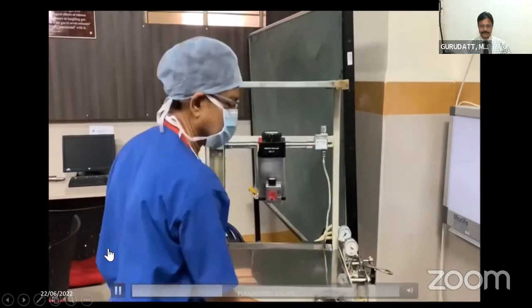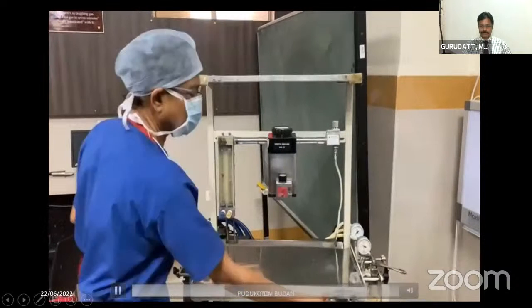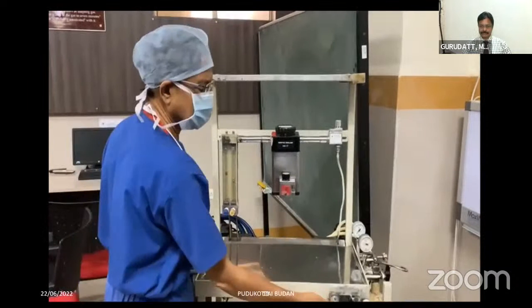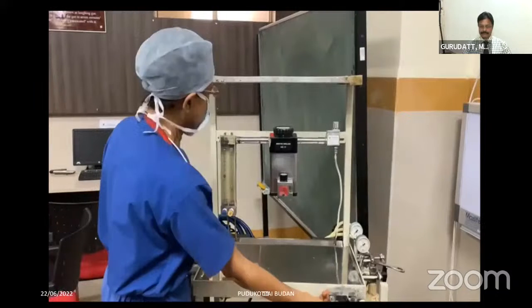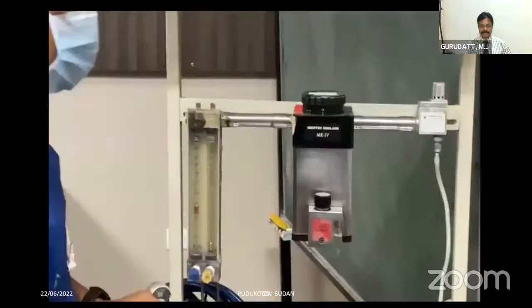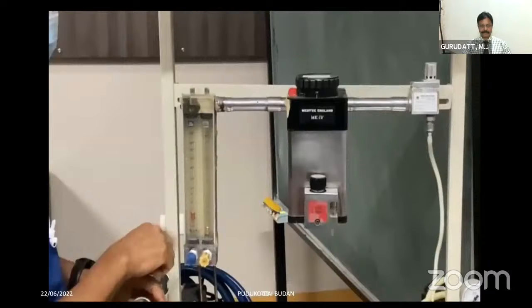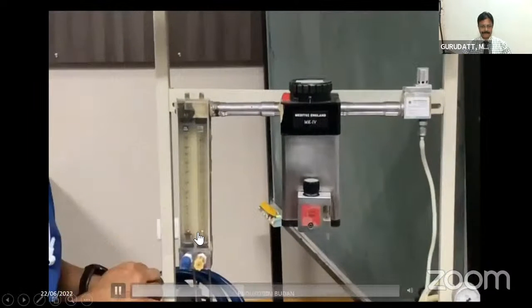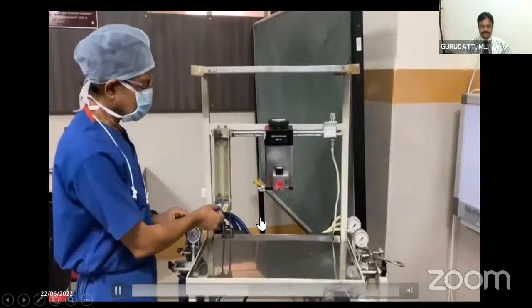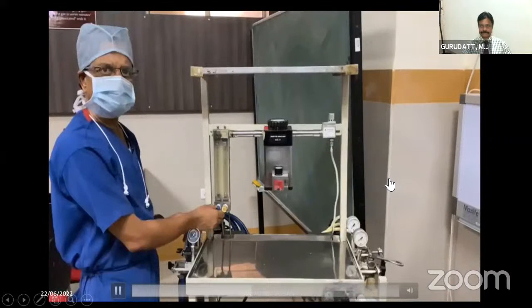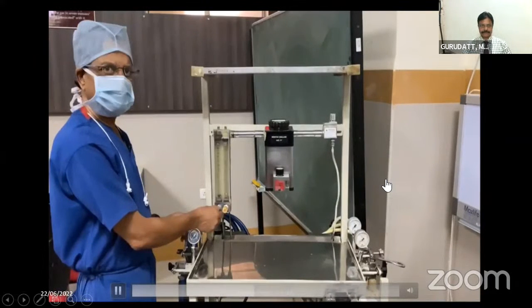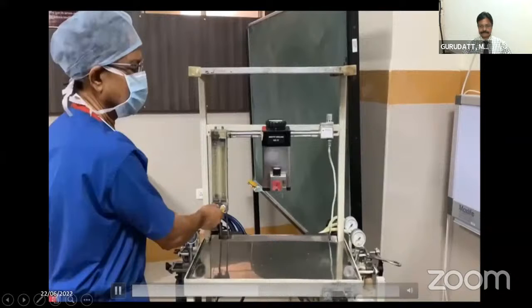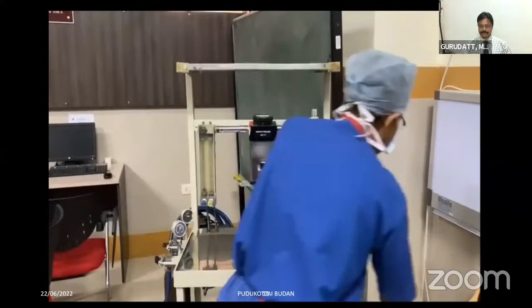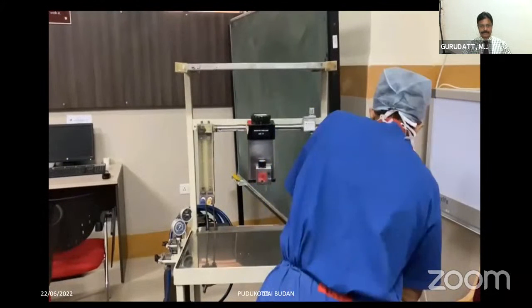Now there is no oxygen flow. I will remove whatever oxygen is there in the piping by pressing the flush. Now you can see nitrous oxide is also falling. Now I am trying to open only nitrous oxide, and I will not be able to open it. So now I am going to open oxygen again. Now I have opened oxygen.